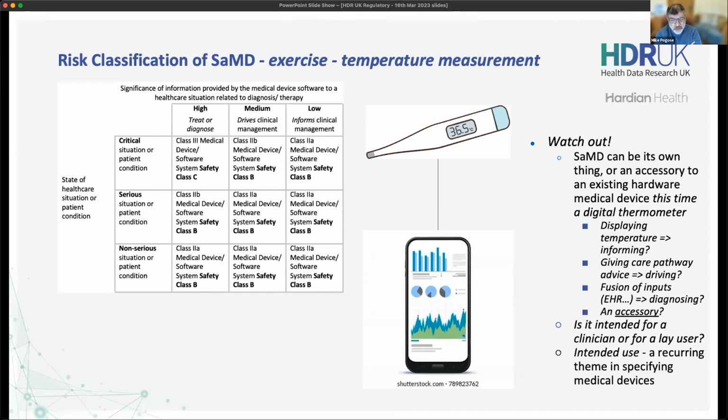What the EU has recently said is expanded on those rules because of other reasons. I think you'll talk about notified body bandwidth later. But basically, you get a time limit of about 2028 to change it. If you are now to produce a new device that hasn't been previously certified, then you've got to think, if it's for the UK, you could get it in as class 1 now and have 3 or 5 years, depending on what the MHRA make their mind up afterwards, to change it to a class 2 if the UK goes this way. If it's a new device for the EU that hasn't been previously certified, it's what it says on the screen. It's going to start at class 2A. So that helps, Ramesh.